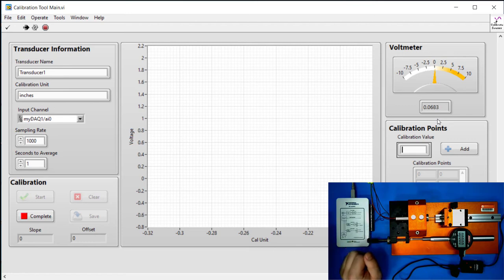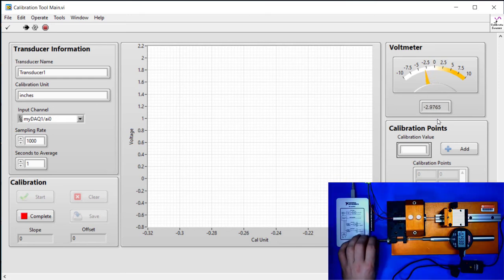Now we're ready to start a calibration. You can do this however you'd like. I like going to one extreme and working all the way up to the other. And then you can work back down. This transducer is a plus or minus ½ inch transducer, so 1 inch total range. And this system is capable of calibrating transducers that are up to 2 inches of travel. So I'm going to go down to about minus ½ inch here, somewhere in that neighborhood. And as you can see in this particular setup, that's producing about minus 5.3 volts.